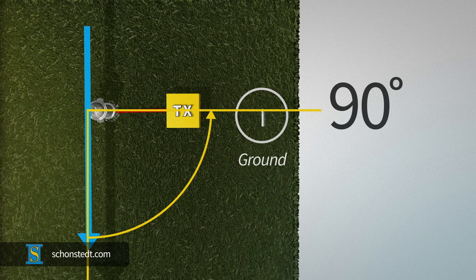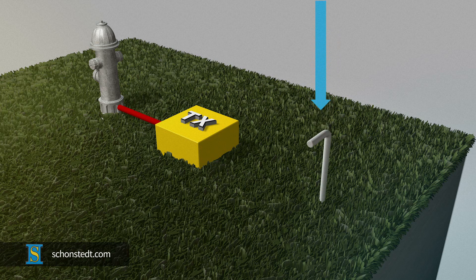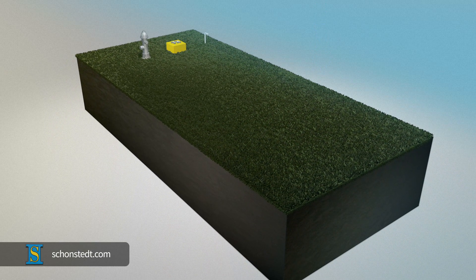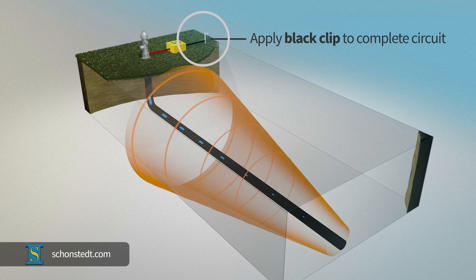Next, position a ground stake as close to 90 degrees as possible to the anticipated line location path. Press the stake deep into the ground to increase surface contact with the soil. Once the ground stake is in position, apply the clip attached to the black cable to the ground stake to complete the circuit.